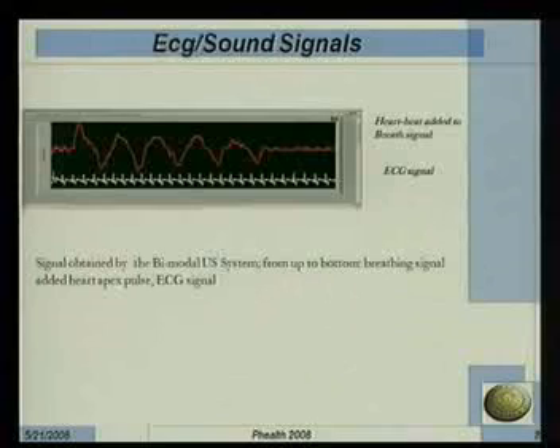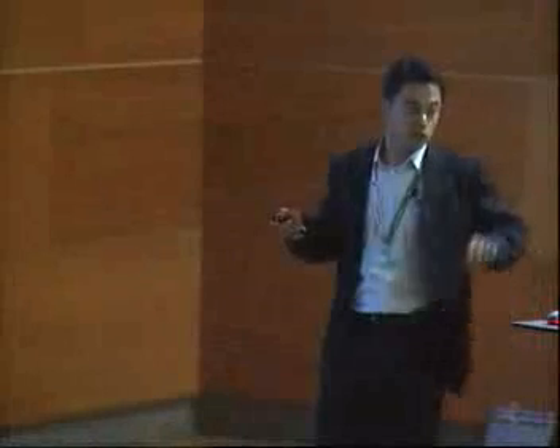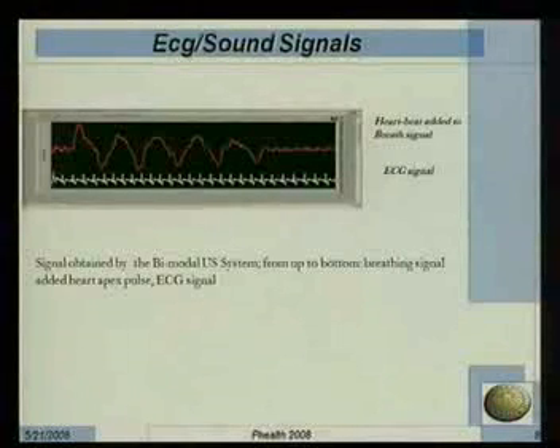In addition to tones, this transducer is able to acquire this type of signals. This is an example of signals acquired by the transducer. This is the heartbeat. This is an overlapping of the heartbeat with the breathing signals. This is a preliminary assessment, of course. Each peak overlapped on the breathing signals corresponds to each QRS complex of the ECG signal, and the ECG signal was acquired simultaneously in order to verify whether the signals acquired by the transducer were reliable.